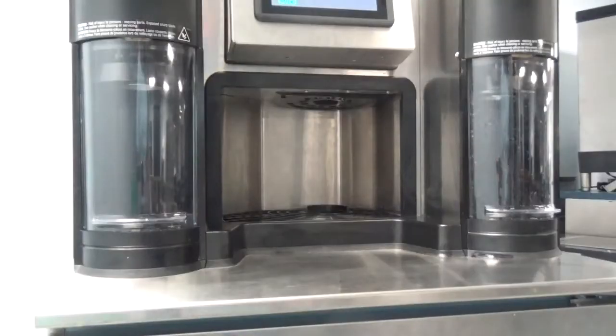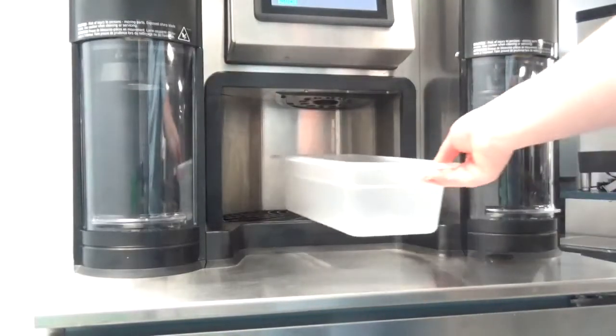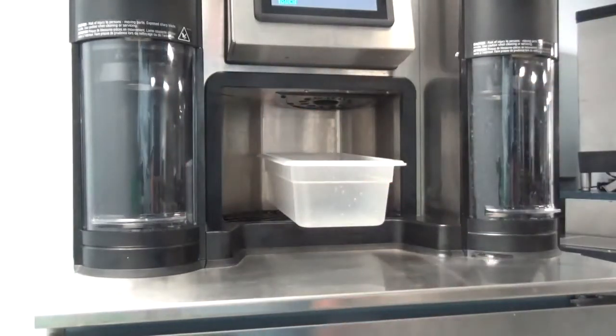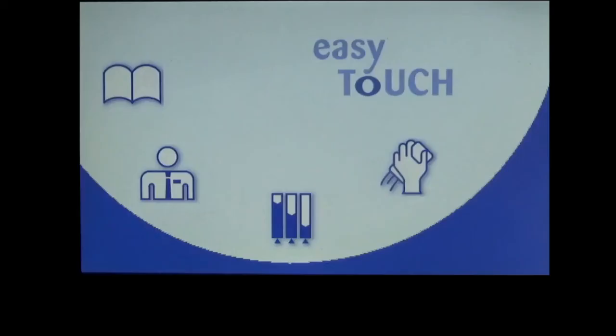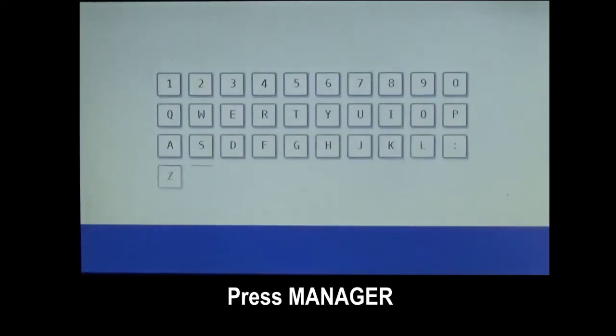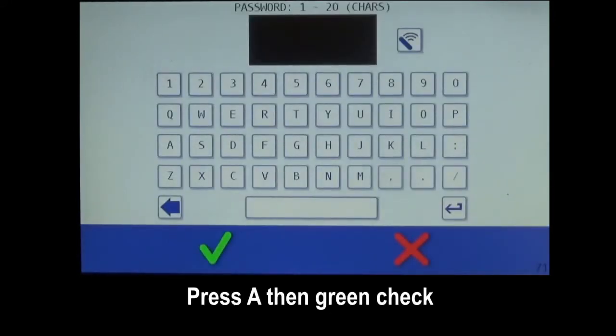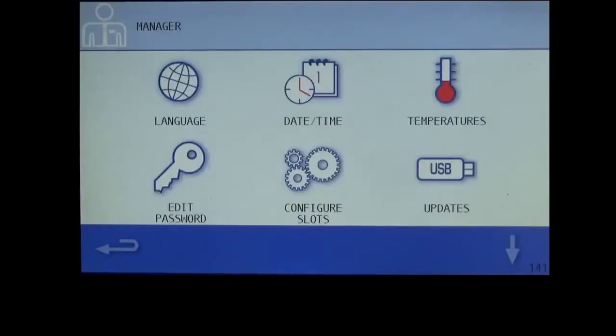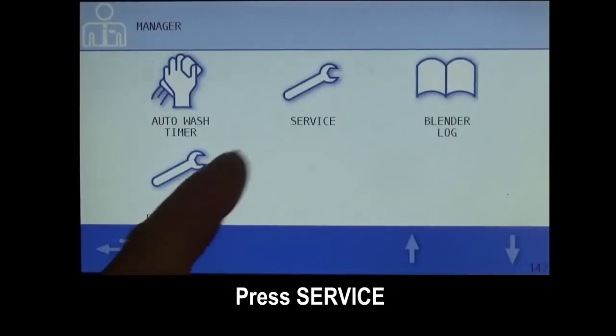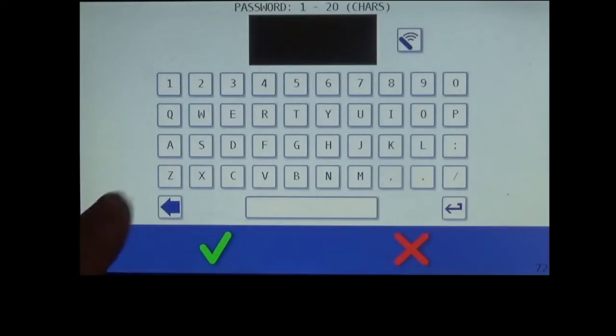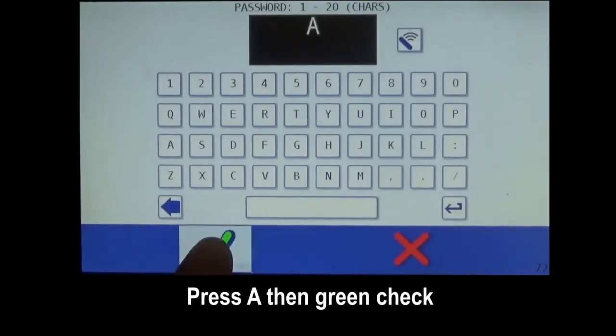To begin testing, place a container in the ice dispense area to collect ice from the dispense test. For MR7 screens, from the Easy Touch screen, press Manager menu. Press A, then the green check. Press the down arrow. Press Service. Press A, then the green check.